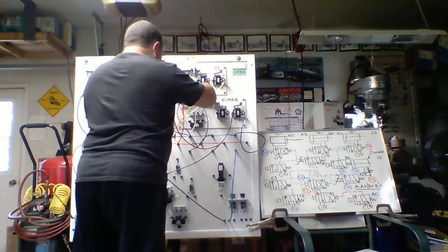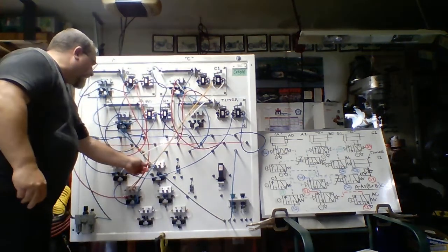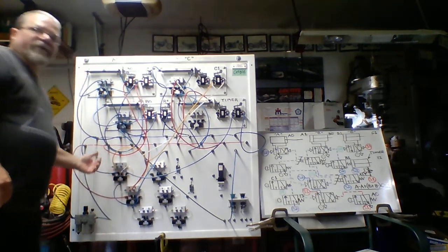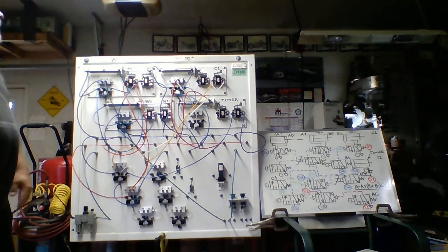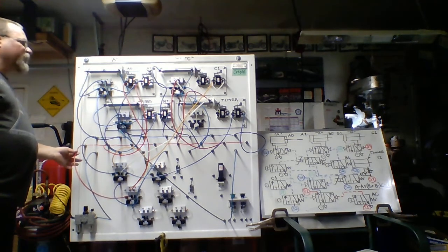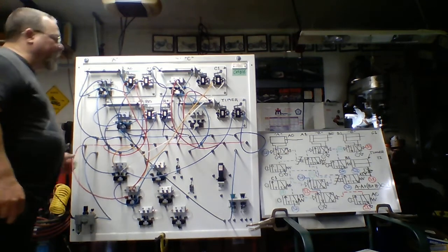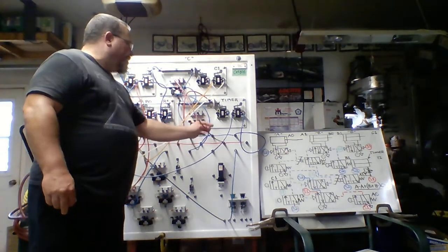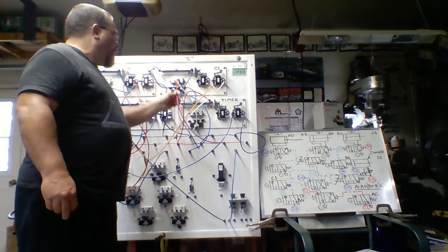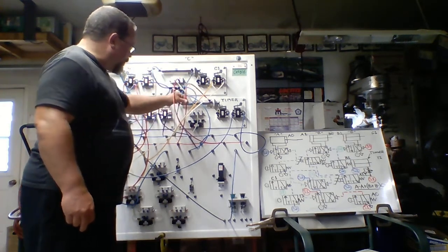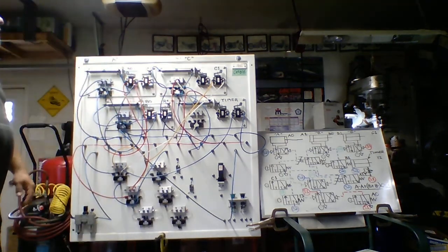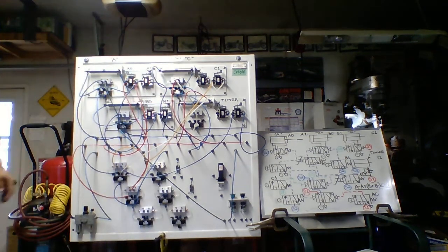And then when we come out of C1, you can see that signal is teed off and it's tied into both cascade valves, which will send them both into home position. So once we do that, we now have energy again back at source 1. So what we did is we come off the manifold directly to source 1. That'll pilot for C to retract. Also, when we look at the timer, it's also plumbed directly to source 1. We'll bring the timer back into home position. So now, let's see the circuit work.